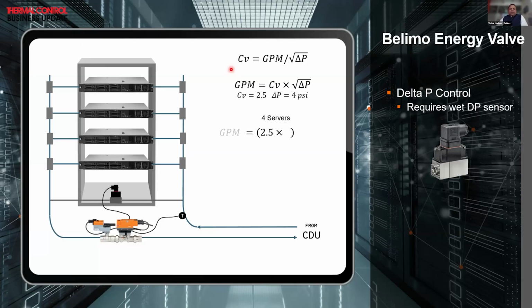And let's put some numbers around. Let's say CV is 2.5, which is a fixed constant because there is no size or dimension change here. And then there is a delta P, which is a differential pressure of 4 psi. So when it comes to a combination of four servers, 2.5 is the CV value, into four servers, into square root of 4, which is the delta P. That comes to 20 GPM, and when it comes to three servers, that comes to 15 GPM. So you can clearly see that whenever we reduce the server racks, the flow is automatically reduced. That's the beauty of having this pressure independent valve in place.